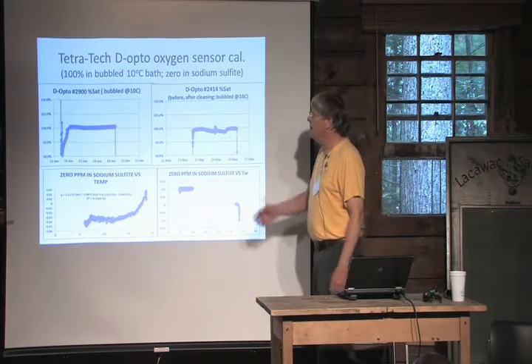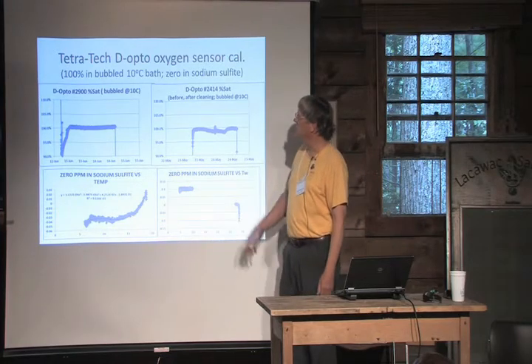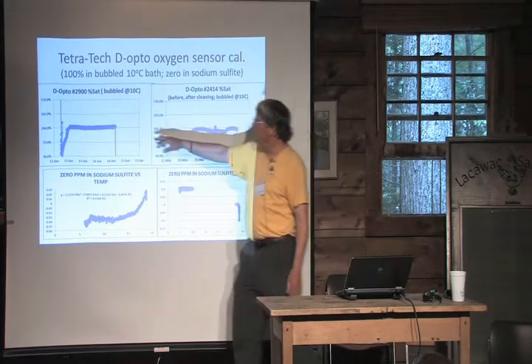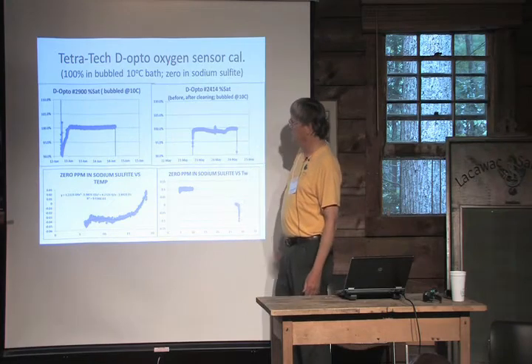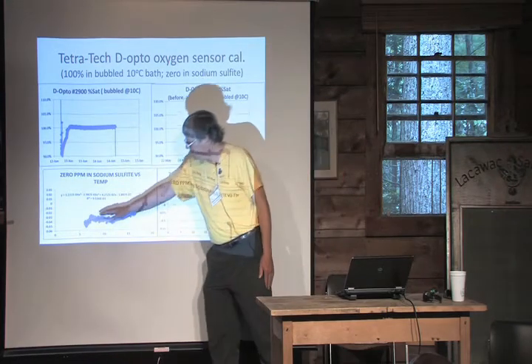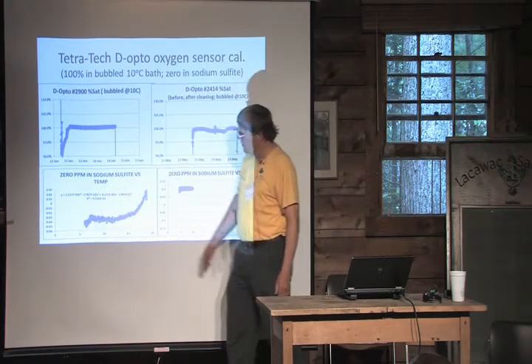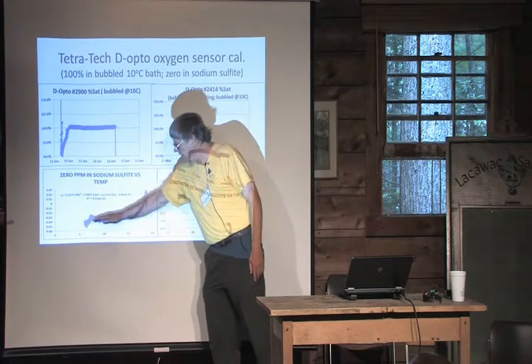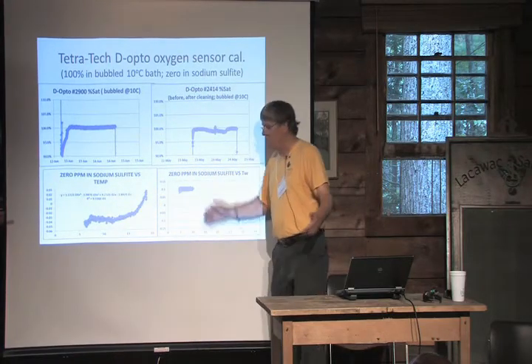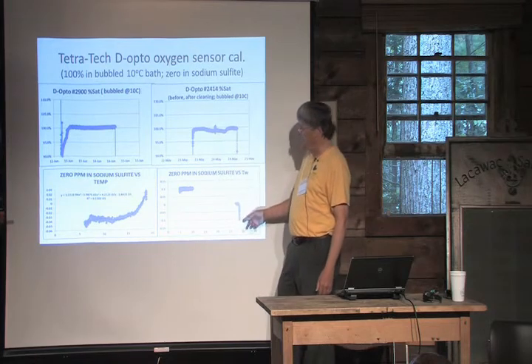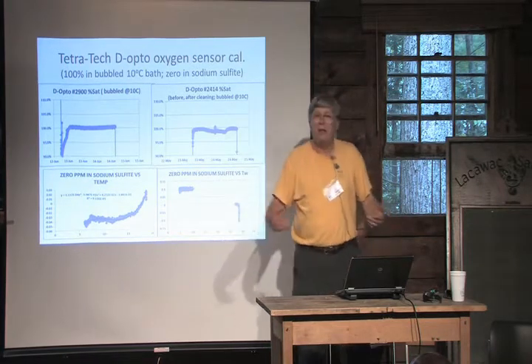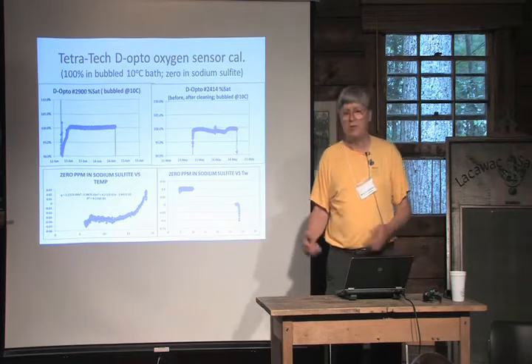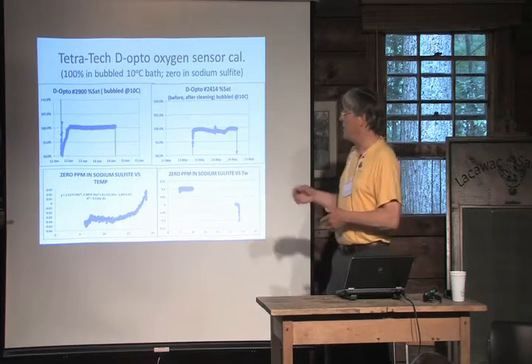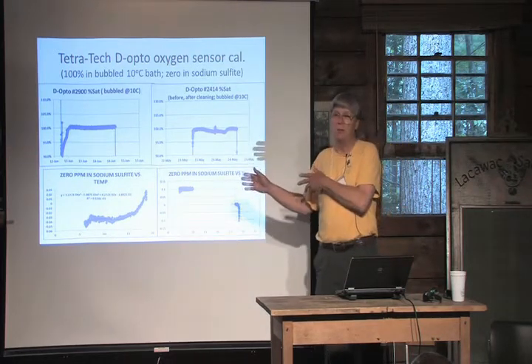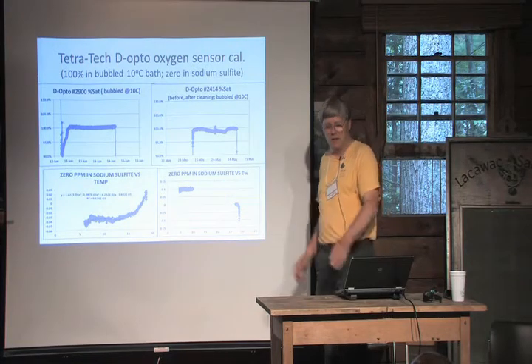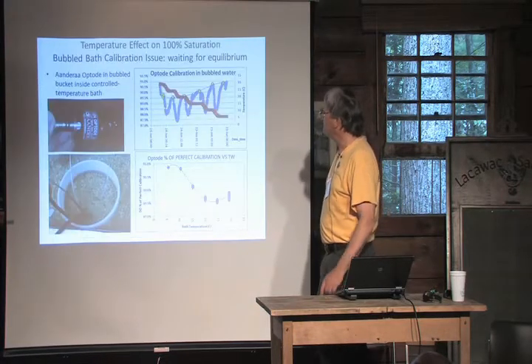Tetra Tech, I did a couple of these D-opto sensors, and they both came out very close to 100%, and small sample. The zero offset looked a little bit more like the Rinko, pretty flat here and then up a little bit at higher temperatures. This was flat here, but then lower at higher temperatures. So there may be an individual variation among the electronics, so it's good to test each one. And I don't know yet whether, once you characterize this, it's always going to be the same or whether it's going to change. So the best thing is to keep testing it each time.